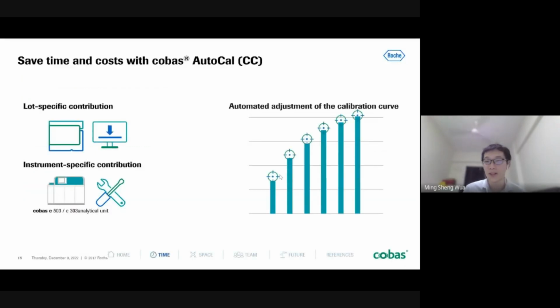The second innovation is something really new, a really new technology, what we call the Cobas Auto Cal, or automated calibration. This is available for the clinical chemistry assays. Imagine with your chemistry analyzers today, let's say you receive a new lot of phosphate. Most of the time you need to do the calibration. For that, you need to go to the fridge, take out your calibrators, which are most likely in lyophilized form.